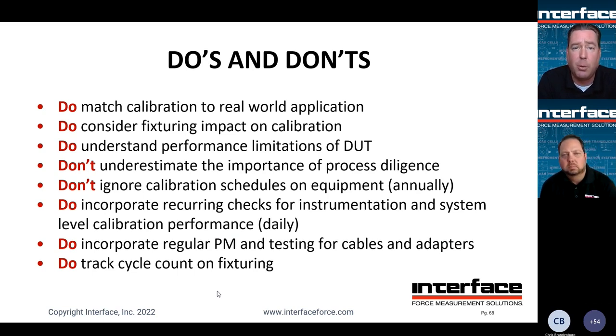Don't underestimate the importance of process diligence, making sure that there is consistency across the workforce in how these calibrations are performed. Don't ignore calibration schedules on equipment on an annual basis. If you have multiple force standards, make sure there is a rotation in place so you're not finding yourself in a production down type environment if your calibration standard goes out for some reason and it's off interval with your rotation load cell. So make sure that steps are in place there.